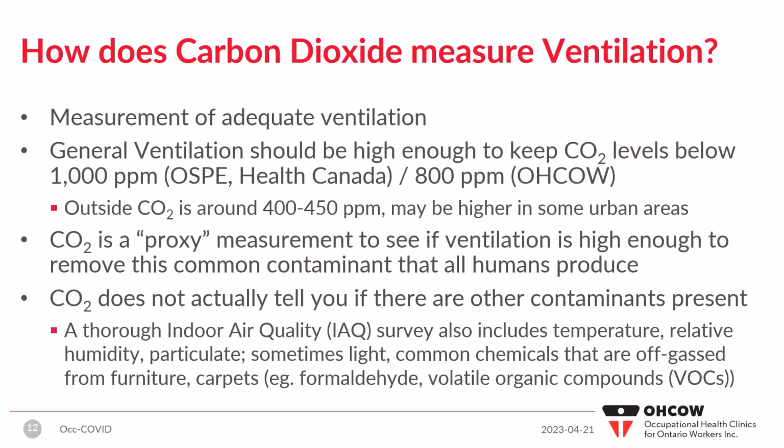These are not toxic levels, because we're using carbon dioxide as a proxy measurement to see if ventilation is high enough to remove the other contaminants that we are actually concerned about, that all humans produce. The CO2 doesn't tell us if other contaminants are present. So a thorough indoor air quality survey is going to look into so much more than just carbon dioxide, but carbon dioxide is a quick and dirty way of actually seeing, okay, is there enough ventilation in there? Should we look into this a little bit more?